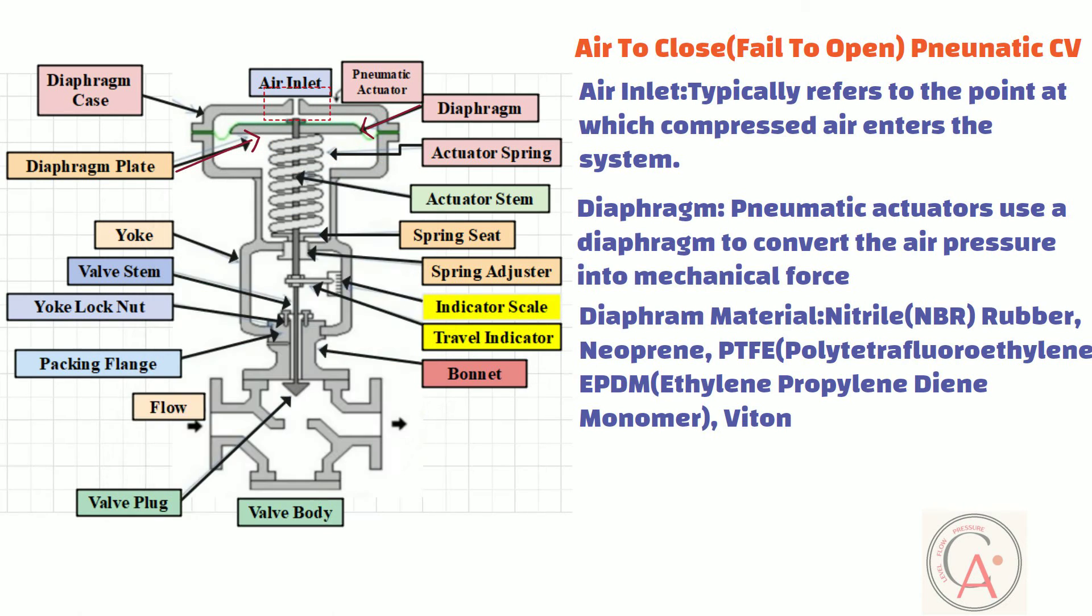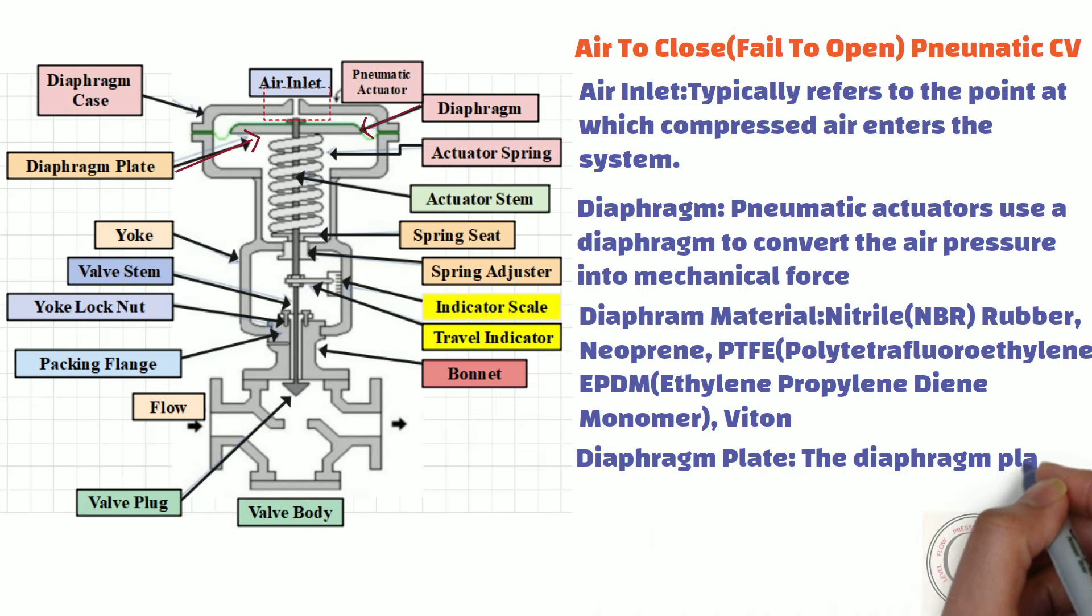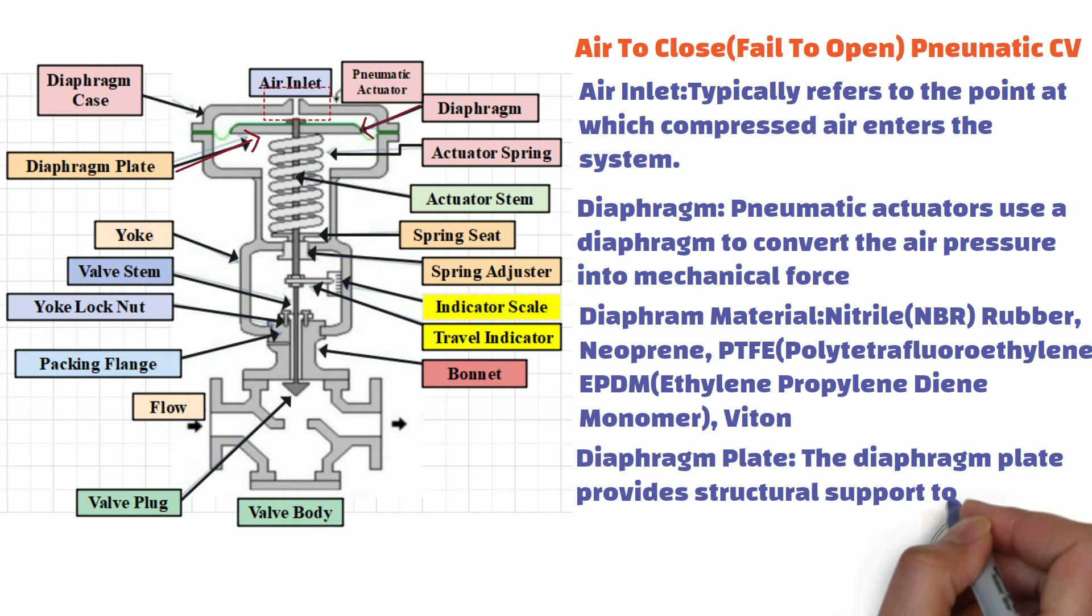As you can see, this part is known as the diaphragm plate. The diaphragm plate provides structural support to the diaphragm. It helps maintain the shape and integrity of the diaphragm, especially when subjected to varying air pressures during valve operation. When compressed air is introduced into the actuator's chamber, it applies force to the diaphragm. The diaphragm plate transmits this force to the valve stem or actuator mechanism, causing the valve to open, close, or modulate according to the control signal received.